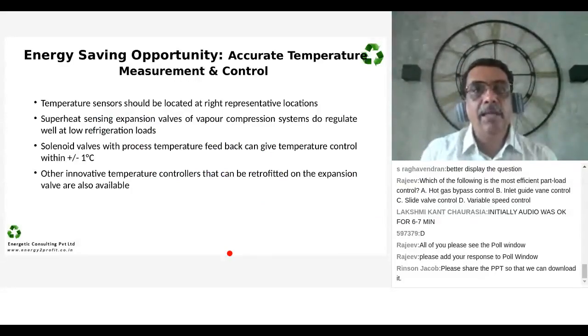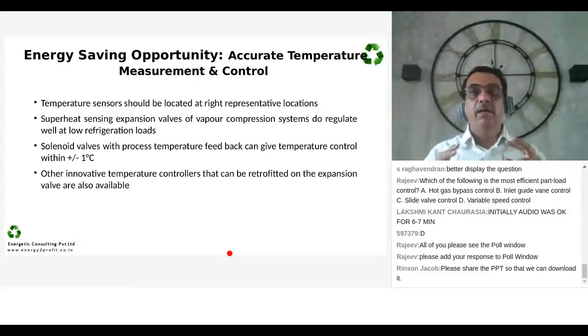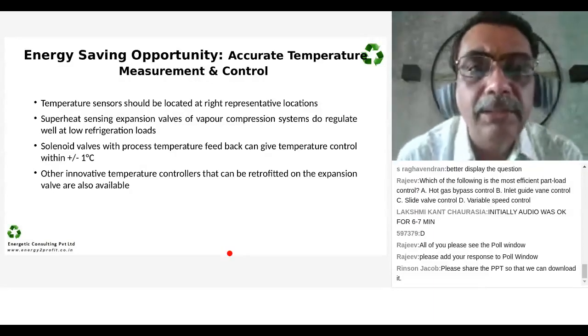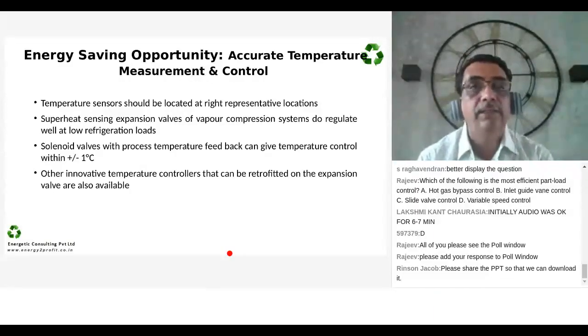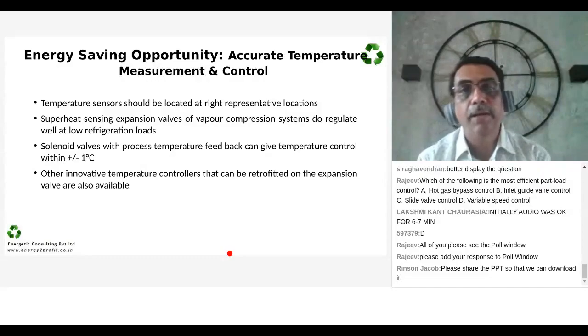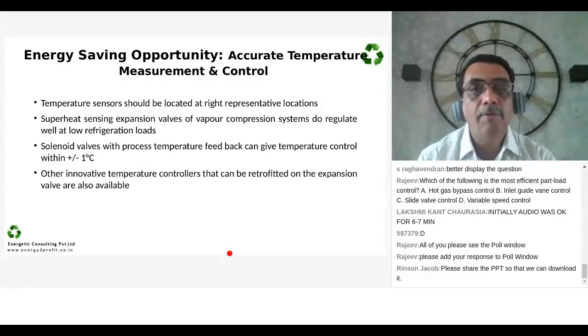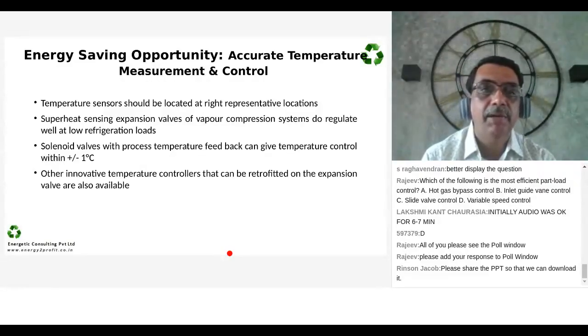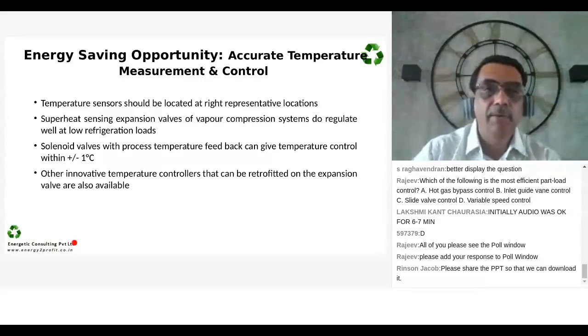Next part is how do you do accurate measurement and control of the temperature? Because temperature, as we saw, is a very, very crucial part. Now you can have temperature sensors located at the right locations. You have sensing of superheat and control. You have a solenoid valve with a process temperature feedback. Depending on the application, it will vary.